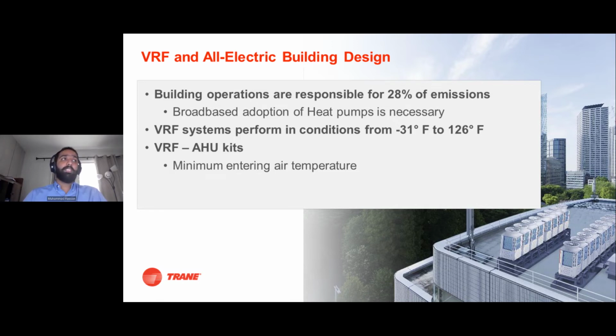The flexibility of VRF systems is being further enhanced now by the capability that's being introduced within the industry to make VRF systems interface with traditional airside products. So we're seeing a lot of applications in schools, especially where unit ventilators are being directly connected to VRF systems, and then that takes care of the ventilation and the heating and cooling as well. It is important to know that these AHU kits typically have a minimum entering air temperature around 0 degrees. So in very cold climates, some kind of preheat might be necessary for these units. And with that, I will turn this back over to Ryan so he can go over some examples of actual VRF projects that he's been a part of.